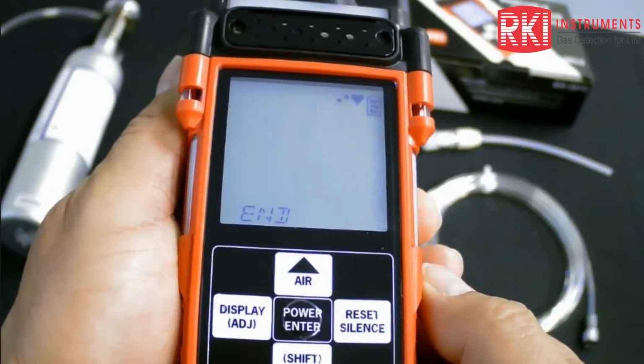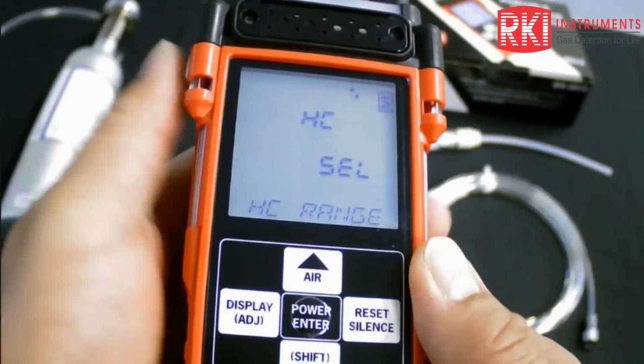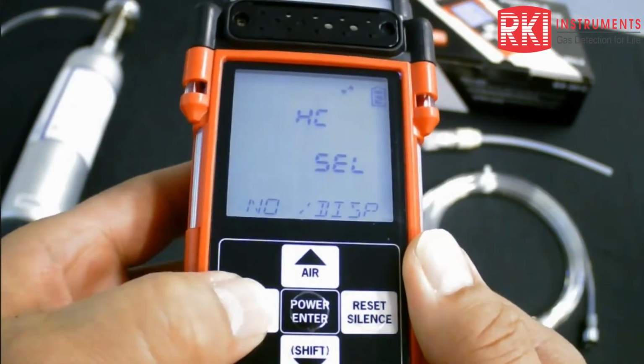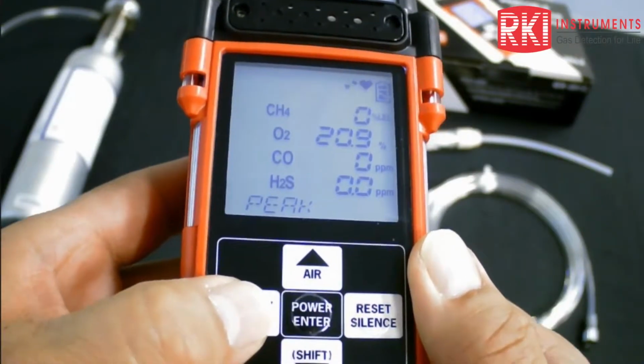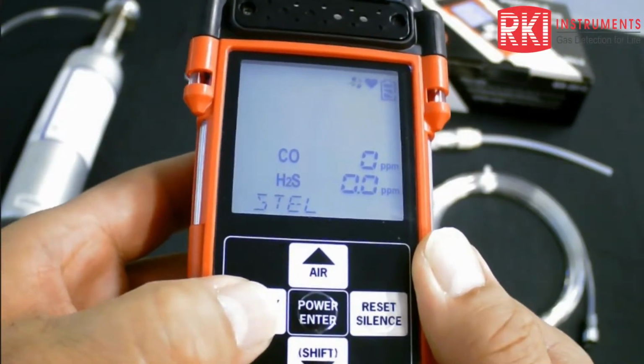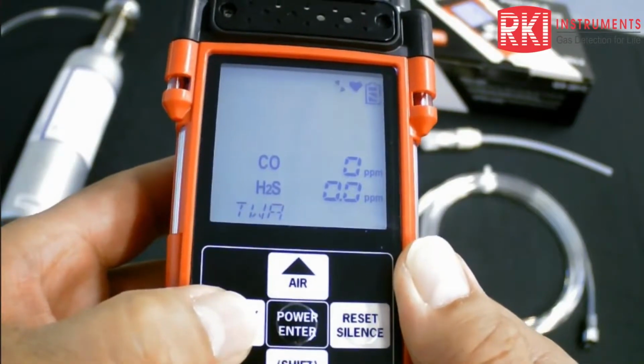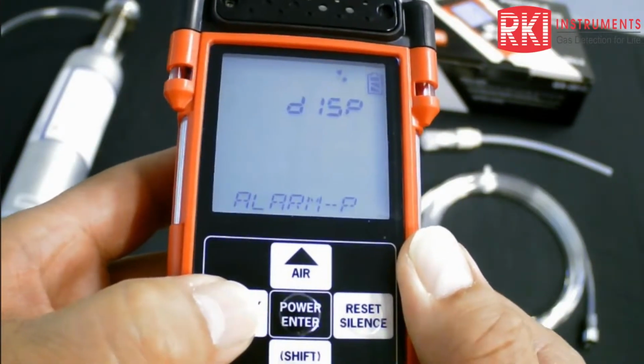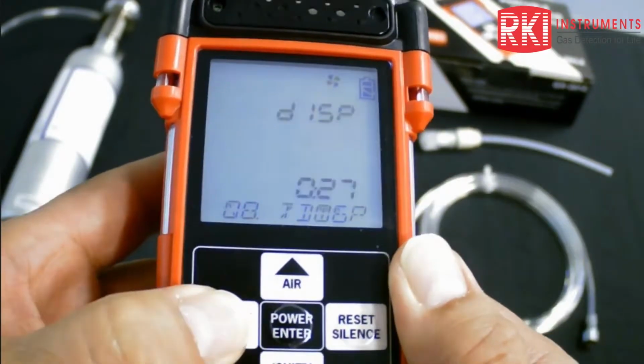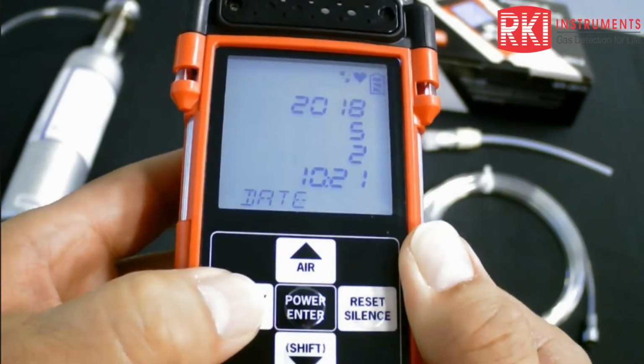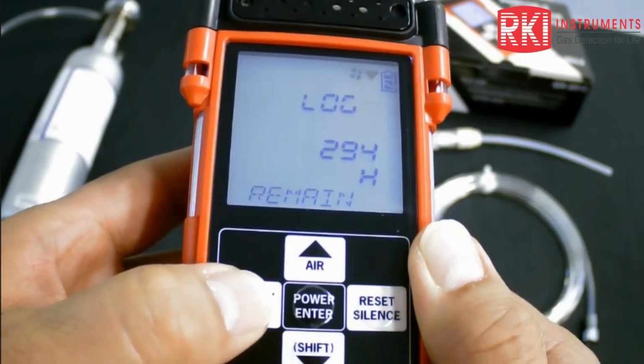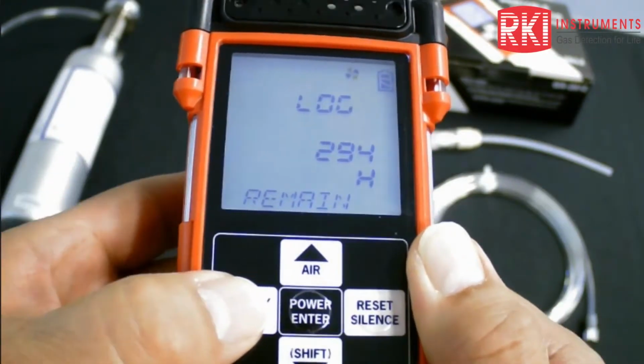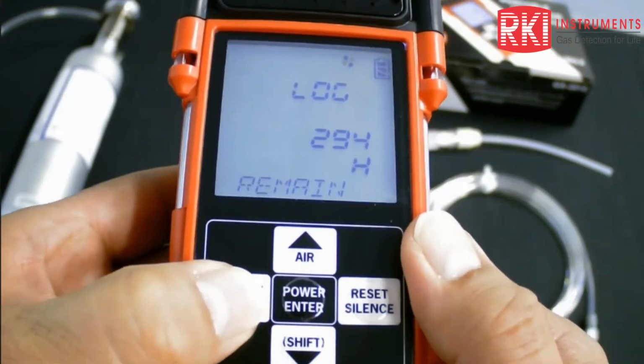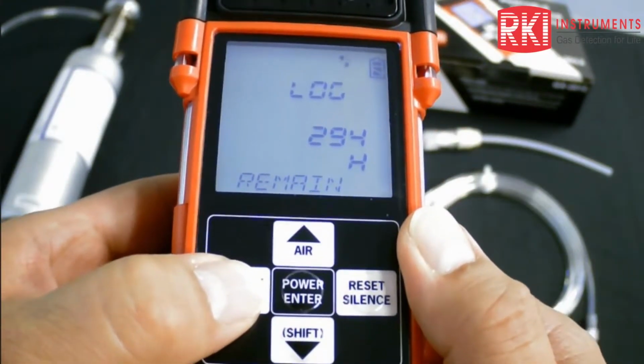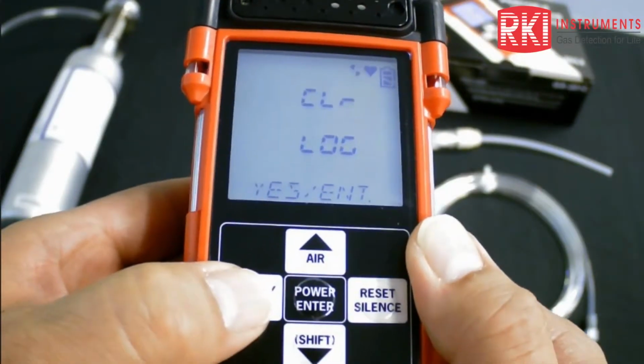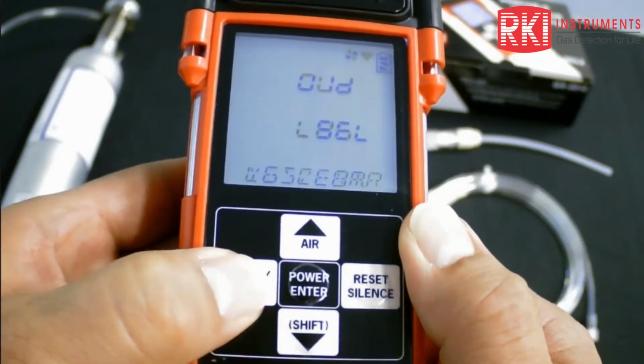Okay, and so HC select, and there's other things in this display range as well. I can go to peak readings, the short-term exposure limit, this is for toxicity levels, time-weighted average, over 8 hours. You have your alarm points can be displayed at startup, time and operation, the date and time, log time, data logging. These units are always data logging. It's up to you whether you want to use that function or not. And they overwrite the oldest information once they get full. Okay. Clear the log. You can clear the data logger if you want.